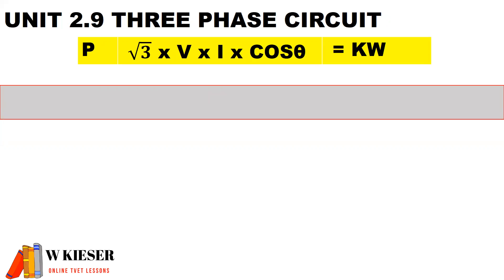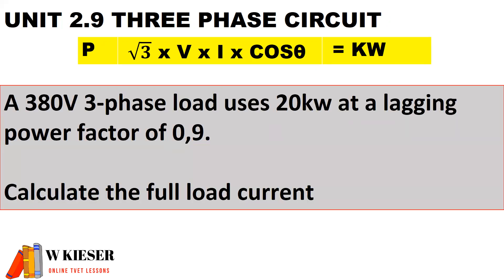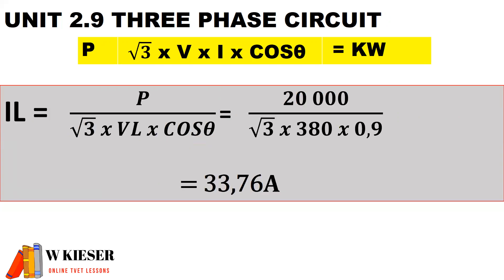When dealing with a three-phase circuit, we multiply by √3 — the rest of the formula remains the same. A 380-volt three-phase load uses 20 kilowatts at a lagging power factor of 0.9. Calculate the full load current. The full load current is the power divided by √3 × voltage × power factor. Therefore, we end up with a load current of 33.76 amps.